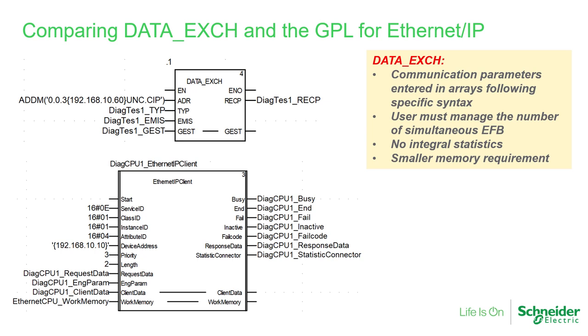The data exchange function block does not include integrated statistics such as the number of successful or erroneous messages, or average communication time. The PLC programmer would need to add logic to calculate these statistics from communication reports, error codes, the activity bit, or transaction numbers. One advantage, however, is a much smaller memory requirement compared to the GPL implementation.